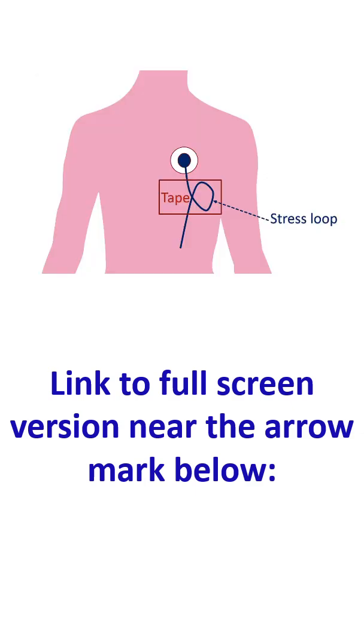The number of electrode patches applied over the chest will depend on whether it is a 2 channel or 3 channel Holter recorder. Color coding of the electrodes may also vary from manufacturer to manufacturer. Positions for attachment may also be changed by your healthcare provider. Electrode patches are connected to the Holter recorder using the leads provided.